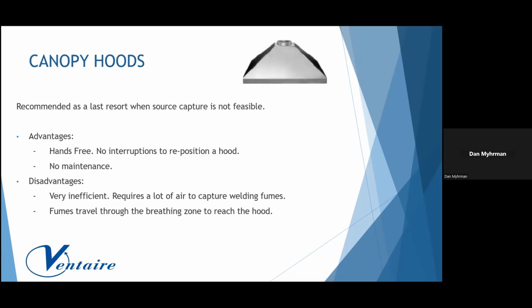I just did a selection for an engineer, and the hood was about 6 feet by 6 feet, and at a 50 feet per minute capture velocity, it needed almost 6,000 CFM. So that's one thing to keep in mind. You can decrease that by enclosing the sides with curtains, but they still require a lot of air. Also, as the fumes travel up into the hood, they pass the breathing zone, so you're still inhaling those fumes. Those are the reasons why I only recommend them as a last resort.